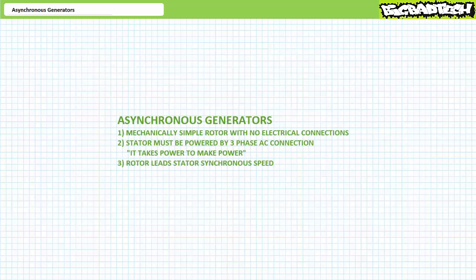In summary, these characteristics define asynchronous generators. One: the rotor is mechanically simple, inexpensive, and necessitates no electrical connection. Two: the stator must be powered by an existing grid connection — it takes power to make power — and the reactive power drawn goes towards establishing the rotating magnetic field, implying asynchronous generators always consume reactive power even when exporting real electrical power. Three: some external prime mover must drive the rotor faster than the stator, i.e., possess a leading slip, for the principle of induction to work.